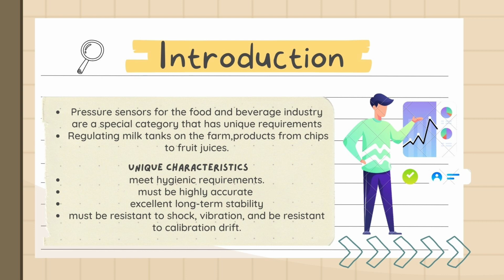sterilization equipment. One of the most unique characteristics that apply to the pressure sensors of the food and beverage industry is that they must meet hygienic requirements. Second, they must be highly accurate and have excellent long-term stability. And also they must be resistant to shock and vibration, and be resistant to calibration drift.